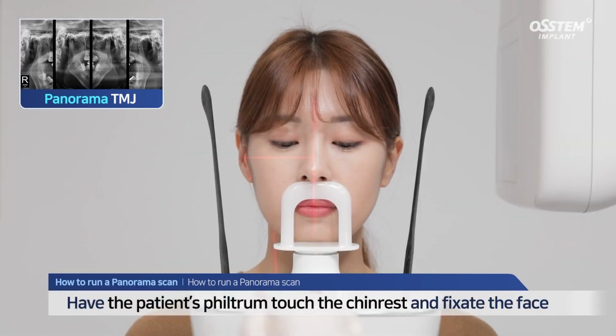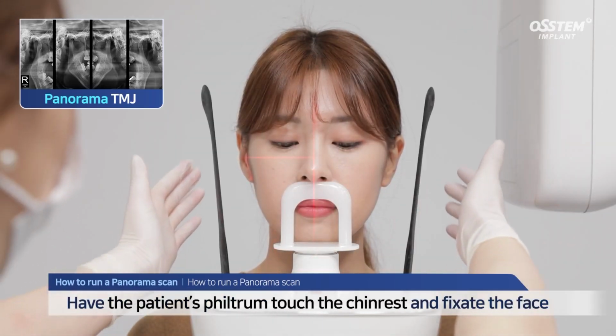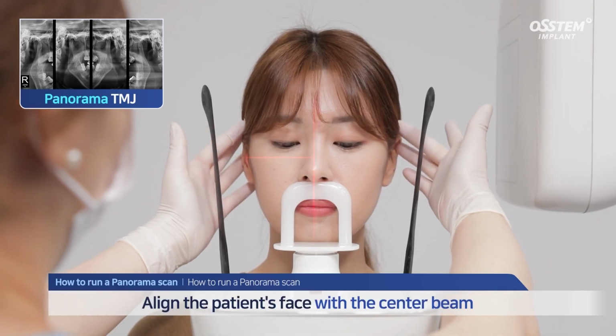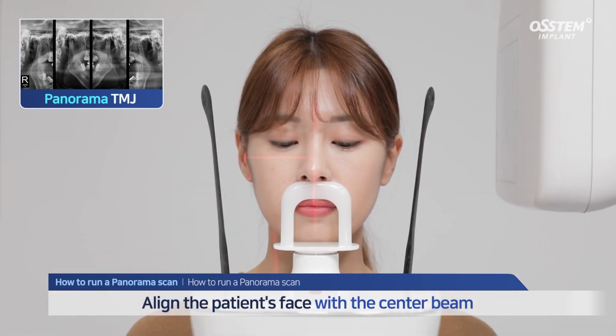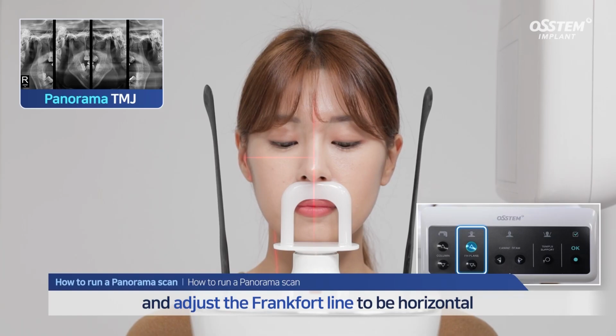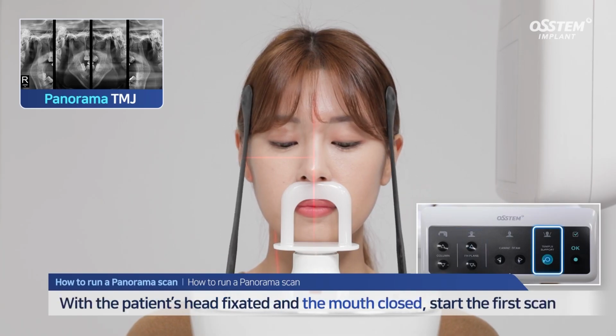Have the patient's philtrum touch the chin rest and fixate the face. Align the patient's face with the center beam. Ensure that the Frankfort line is horizontal. With the patient's head fixated and the mouth closed, start the first scan.